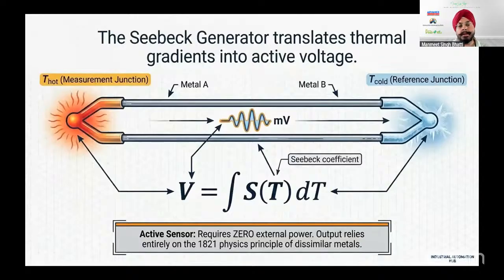Now, cold junction, people assume that if my cold junction is outside the process, it will stay that way. But that is not the case. Cold junction temperature also rises or reduces. It also plays its role in the millivolt coming. Imagine you have a thermocouple which is put into a furnace where it is going to measure 200-degree temperature, and your cold junction is outside where the ambient temperature was actually 45 degrees, but due to the heat, that 45 has gone to 50. So your cold junction has actually increased by 5 degrees. Okay, so your millivolt will be in error, and you will be telling me that my temperature measurement is not accurate. Actually, it's accurate, but you have not gone for cold junction compensation.